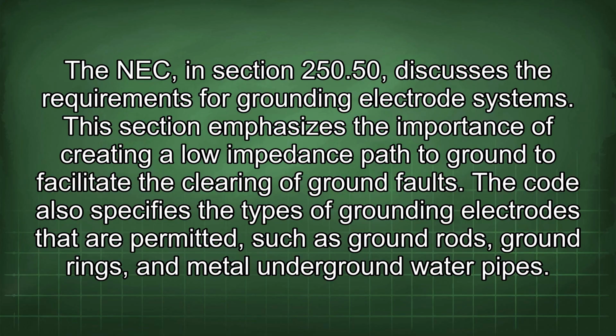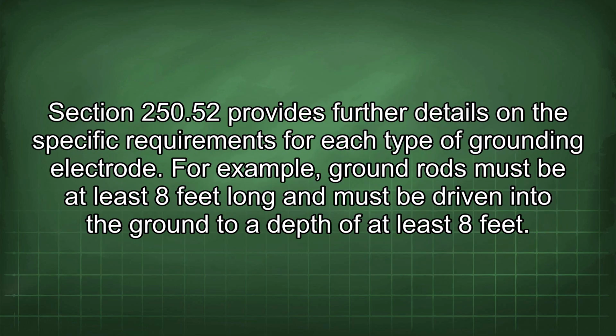This section emphasizes the importance of creating a low impedance path to ground to facilitate the clearing of ground faults. The code also specifies the types of grounding electrodes that are permitted, such as ground rods, ground rings, and metal underground water pipes. Section 250.52 provides further details and the specific requirements for each type of grounding electrode. For example, ground rods must be at least 8 feet long and must be driven into the ground to a depth of at least 8 feet.